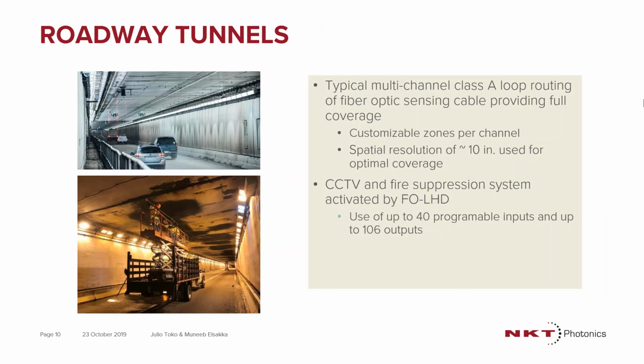Roadway tunnels are definitely a point of interest for protection for fiber optics. You have the flexibility with the customizable zones per channel to really pinpoint accurately where along the full length of the cable you have a hazard, obviously in the event of a heat or fire event. You have the spatial resolution of 10 inches, and you can customize these zones as required. You also have access to CCTV and fire suppression systems, which can be activated by a fiber optic linear heat detection system. By the use of programmable inputs and outputs, you can also interface with any third-party ventilation systems and CCTV in the tunnel.